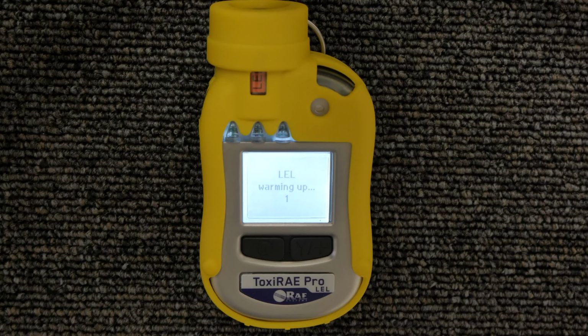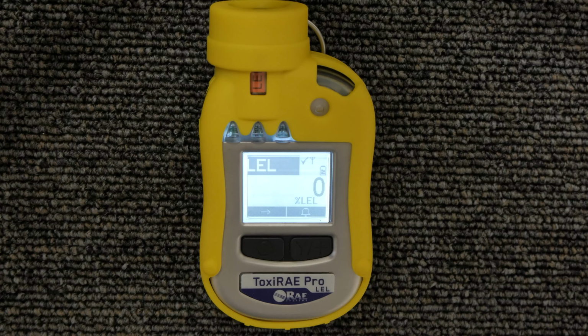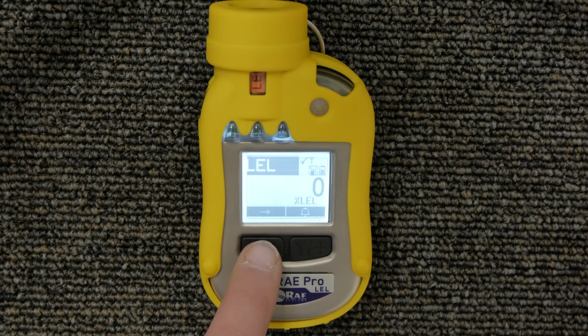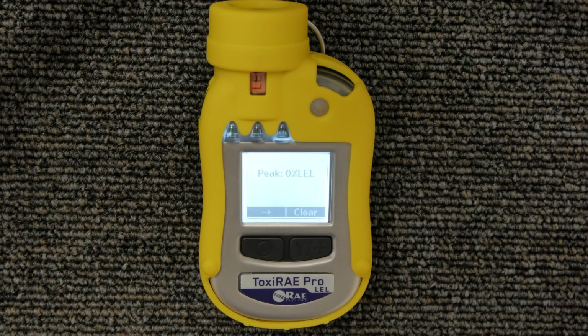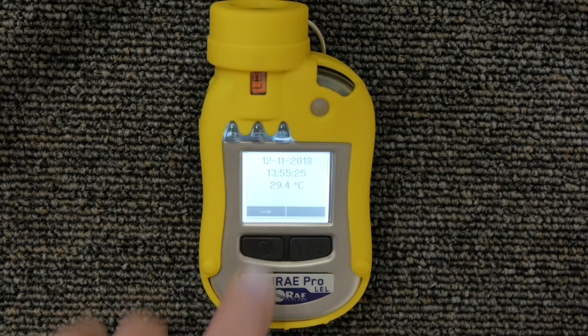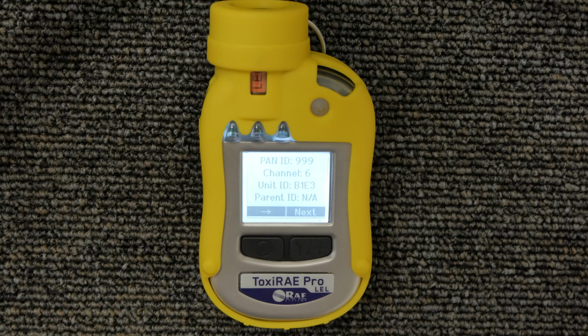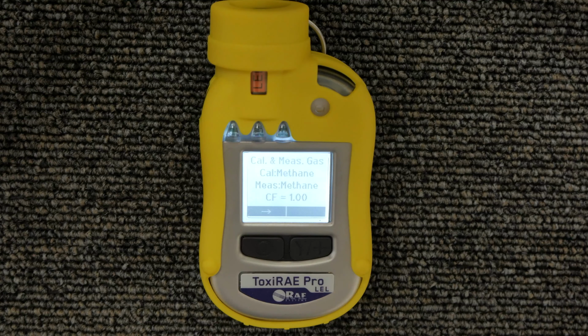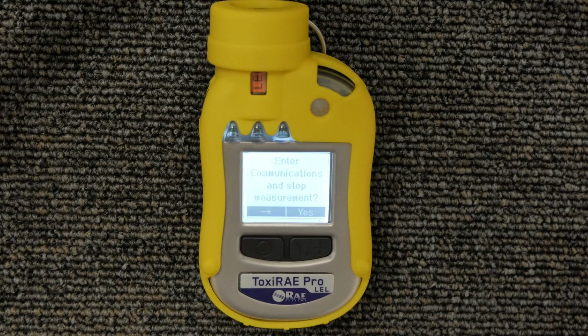And in order to communicate with the AutoRAE 2, you have to scroll through the menu by hitting the power button a few times. You will see the peak, the time and date, and the wireless if you have the wireless set up. And also the measurement gas and calibration gas used for the meter. Enter communications and stop measurement, hit the Y plus button or the yes button. And your unit is now ready to communicate with the AutoRAE 2 controller.